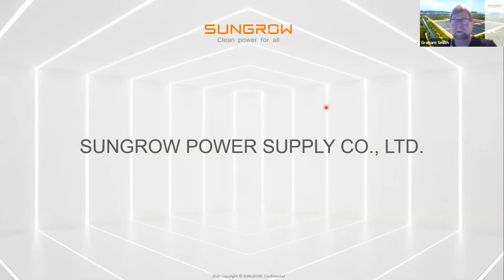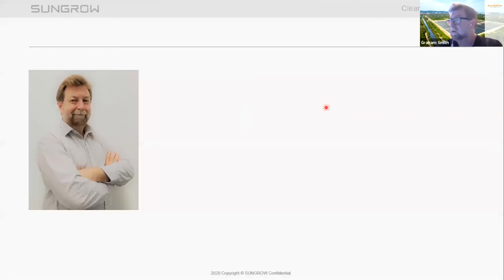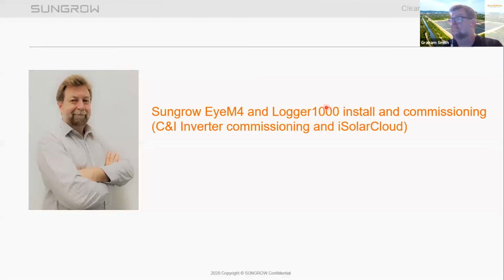All right, so what I'm going to cover today is more of an installer focus, and I'm going to cover commissioning the CNI range via the EyeM4 dongle and/or Logger 1000. Now, it is an installer module on its own. I would normally take about 45 minutes, so I'll try and speed up a little bit to keep it down to half an hour. And if you've got any questions, we can go through them at the end.